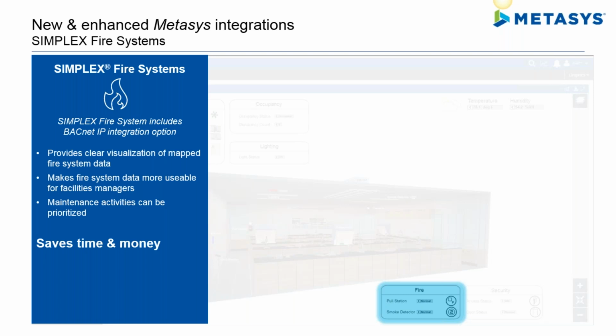By focusing on integrating only the kinds of information that would be useful and usable by a facility manager, in the example I'm showing here of the Metasys UI, the smoke detectors and pull stations are visualized where they are actually located in that space, and the status boxes indicate that they're operating normally, or they could be showing that they are in need of maintenance attention, for example, if the smoke heads are dirty.